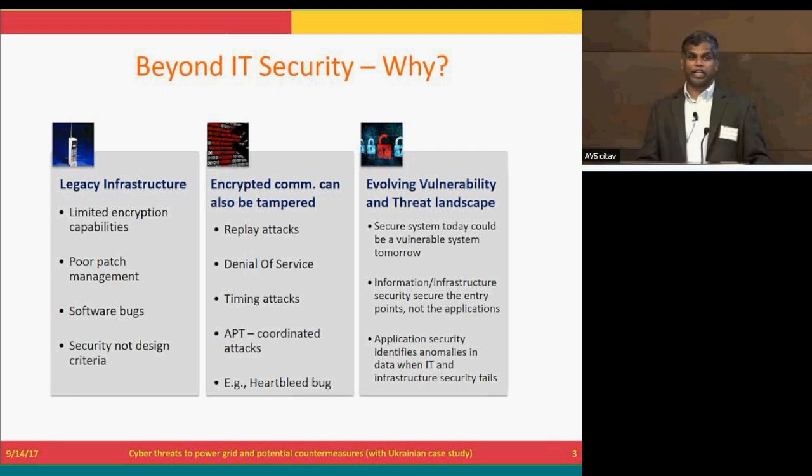The encrypted communication itself, as I was telling before, could be subject to attacks like replay attack, denial of service attack, timing attack, just to perturb the timing between packets. That can create malfunction depending upon the critical application. If some critical application operates in milliseconds, like protection applications, and you play with the timing, then the whole thing can be impacted in a negative way.